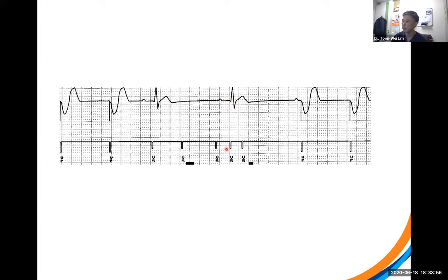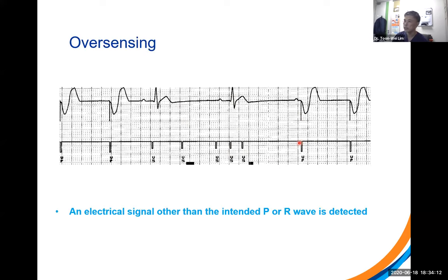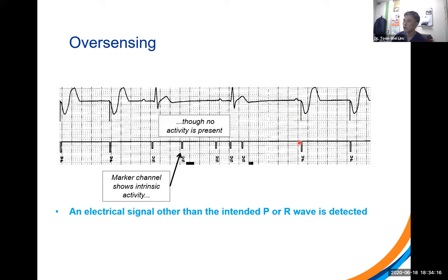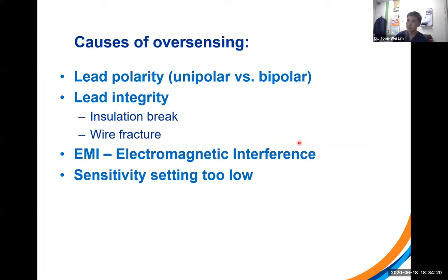That's because, other than sensing the intrinsic electrical activity, as you can see by the annotation markings down here, the device is also sensing things that don't exist. In this case, this is probably sensing of the T wave. When you have sensed activity here, it inhibits the pacing of a demand pacemaker and the pacing spike is greatly delayed. This is what we call oversensing, and you can tell by looking at the intrinsic channel marker, where it is sensing in spite of no activity. So what are the common causes of oversensing?